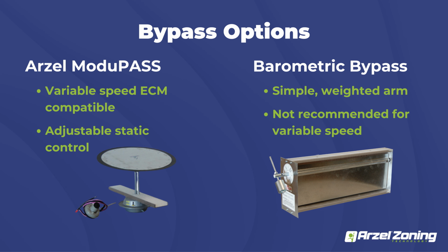If you guys ever need to size bypass as well, you can download our bypass sizing charts right on our website. Just go to arzelzoning.com, click on products and dampers, and go about halfway down. It'll have bypass sizing chart. You can download that. It'll actually size the bypass for you. All you guys need to know is the tonnage of the equipment, if you guys are doing branch or trunk dampers, and then your smallest zone CFM, and it'll tell you what size bypass to use. Otherwise, if you guys don't want to do that, you can always call us at tech support. We'll tell you exactly what size bypass, as long as you have that information for us.